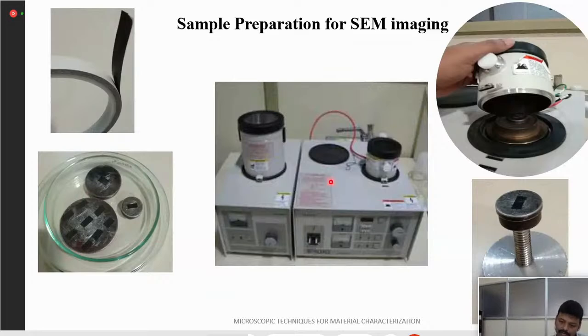Before going for analysis, we should understand 2 points. One, the sample should be completely dry, because the instrument is working with high vacuum. During our discussion about the principle, I told you the instrument is working under high vacuum. So obviously, we will be using a completely dried sample for analysis. Without drying, we can't use it. There are some other methods, the variable pressure mode scanning electron microscope and environmental SEM. There we can look at samples with a little bit of water content also.